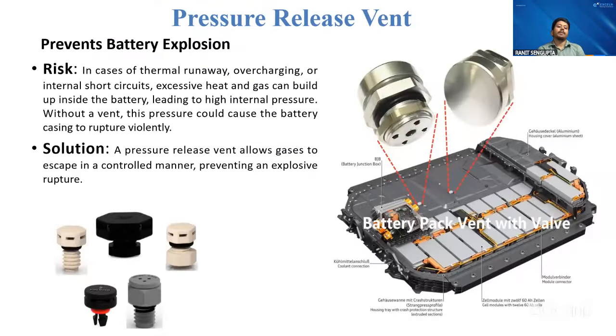This is the pressure release valve or vent we are using in the battery pack. In case of four-wheeler battery packs, you can see on the top cover or outer cabinet we use this type of pressure release vent. We can use 2 to 3 depending on your application purpose - how much pressure your battery can create during thermal runaway determines the number of pressure vents you need. Most pressure release vents are IP67 or IP68 rated, meaning no water particles can move through this pressure release vent.